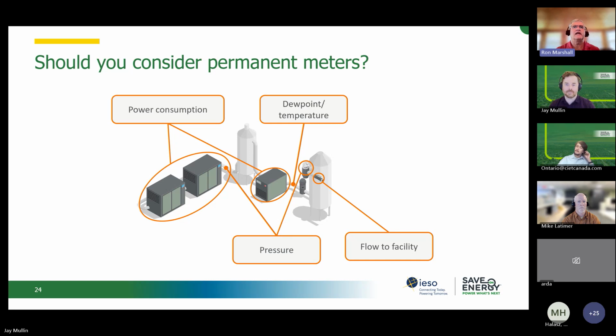characteristics, but it's better to have an actual flow meter showing what's going into the plant, and that tells you all kinds of stuff. And then if air quality is important to you, measuring the dew point coming out of the system and/or the temperature of the air going into the air dryer is quite important too if you want to maintain the high quality of air so that you don't have contamination. So I would suggest that any system of anything over 100 horsepower should have permanent meters running into some sort of data collecting device. There's various manufacturers that can offer that to you, so that you can have a system like that.